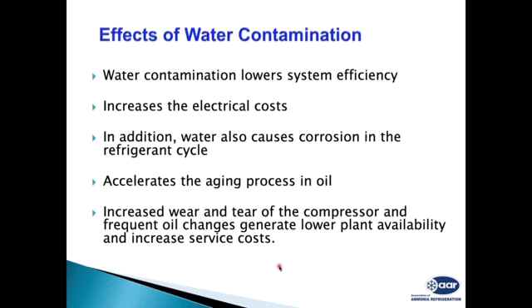Now, because of this water, as we have seen, the ammonia pressure-temperature chart does not hold good. The ammonia temperature rises when it is mixed with water; typically, for 10% water in ammonia, there is about a 2 degrees centigrade rise. To compensate for this rise in temperature, we have to operate at a lower suction pressure of the compressor. I have to have additional refrigeration capacity, which reduces system efficiency and increases electricity cost.